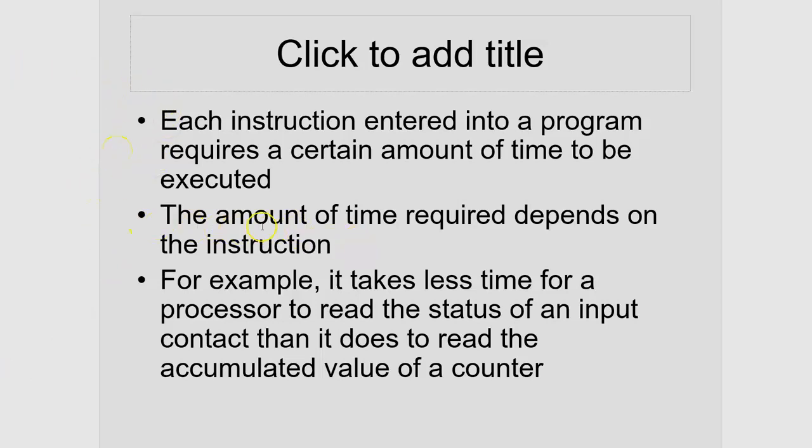The amount of time required depends on the instruction. It depends on the logic that you have. If you have a lot of AND or OR logic on a certain rung, it takes time to go through that logic. So depending on the number of instructions and the type of logic you have on the rung, that's going to affect the time required to update the input and output image tables.